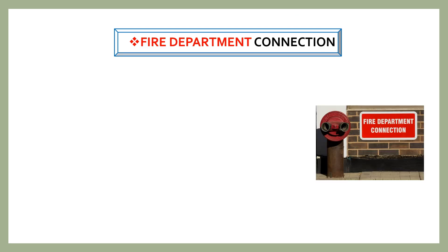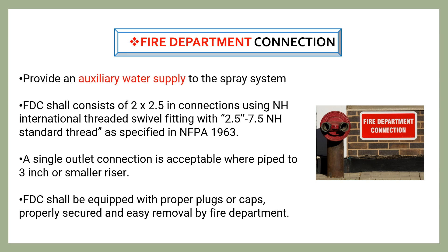The Fire Department Connection (FDC) is used as an auxiliary water supply to the spray system. The FDC shall consist of 2 by 2.5-inch connections using NH international threaded swivel fittings as specified in NFPA 1963. A single outlet connection is also acceptable where pipe connects to a 3-inch or smaller riser. The FDC shall be equipped with plugs or caps properly secured for easy removal by the fire department.